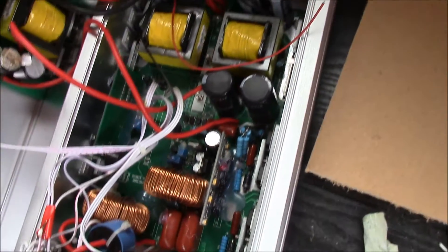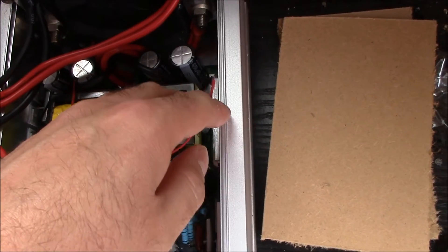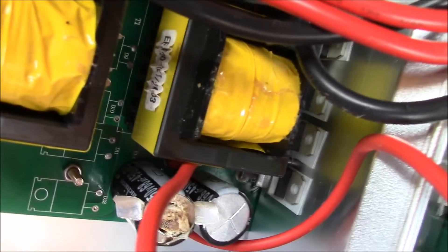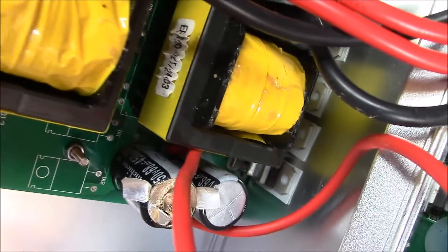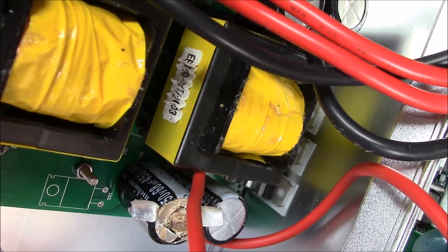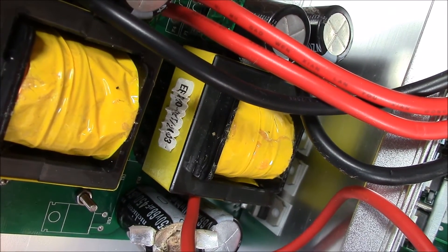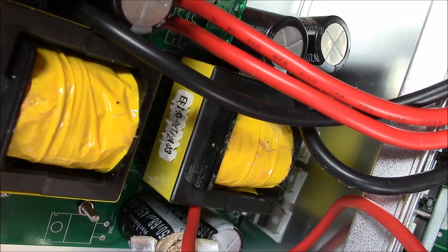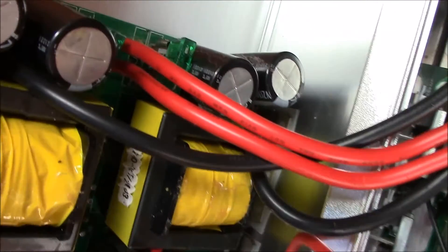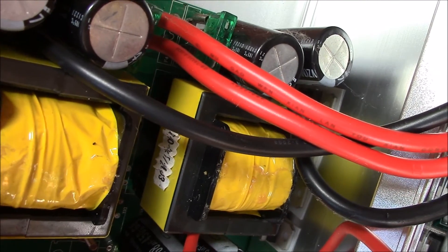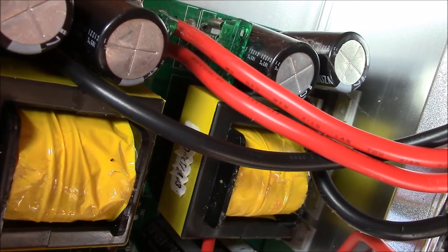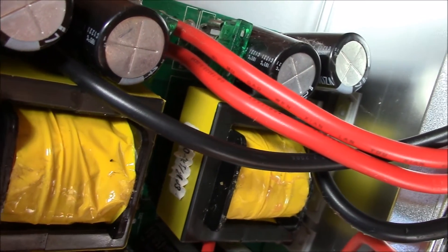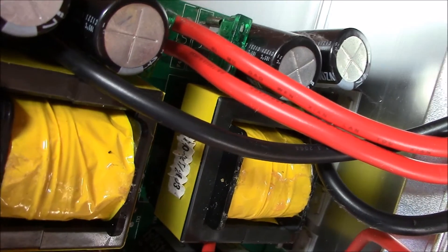So what I'll do, because I need this inverter to run, I will put it back together again as it is, with notes taken that there is a fan broken and that I need to get a capacitor. So I need to take a note of what the capacitor is. It's a 68 microfarad at 450 volts.